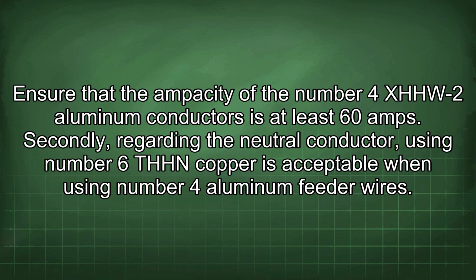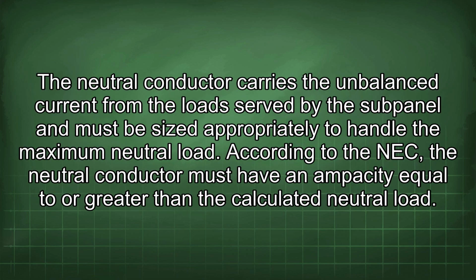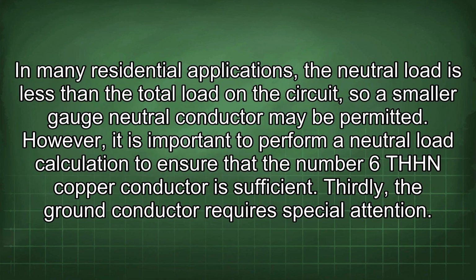Secondly, regarding the neutral conductor, using number 6 THHN copper is acceptable when using number 4 aluminum feeder wires. The neutral conductor carries the unbalanced current from the load served by the subpanel and must be sized appropriately to handle the maximum neutral load. According to the NEC, the neutral conductor must have an ampacity equal to or greater than the calculated neutral load. In many residential applications, the neutral load is less than the total load in the circuit, so a smaller gauge neutral conductor may be permitted. However, it is important to perform a neutral load calculation to ensure that the number 6 THHN copper conductor is sufficient.